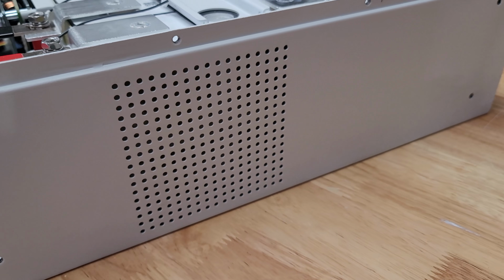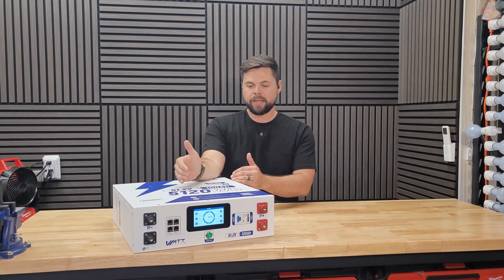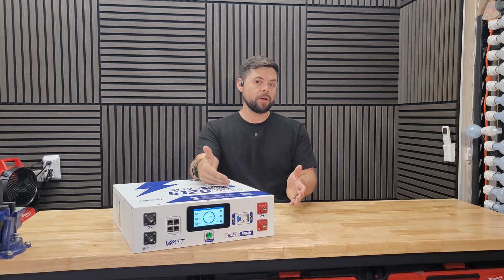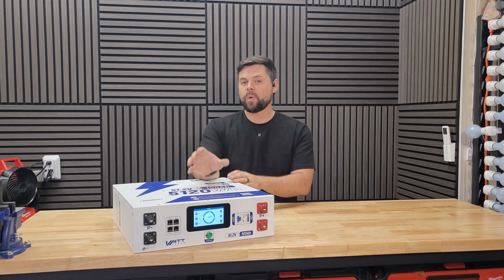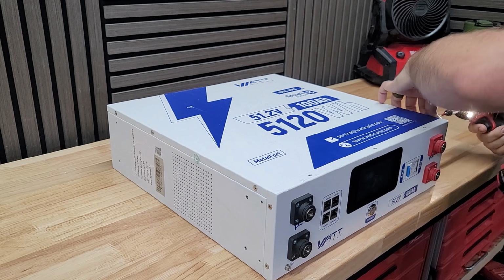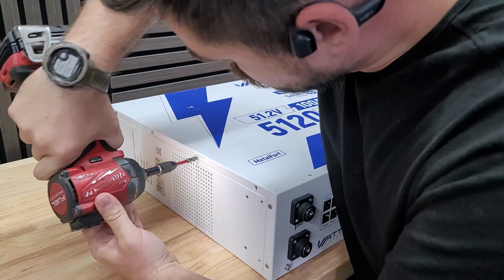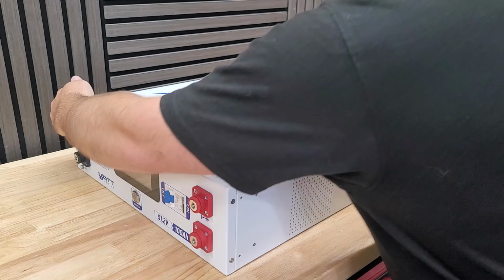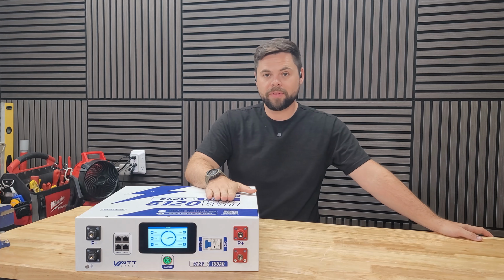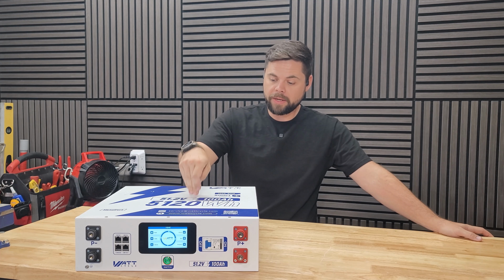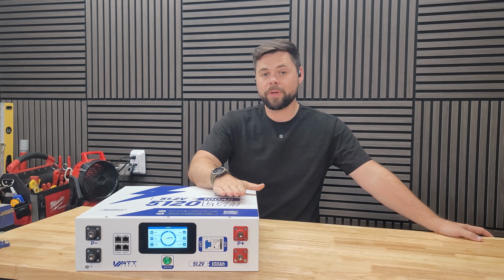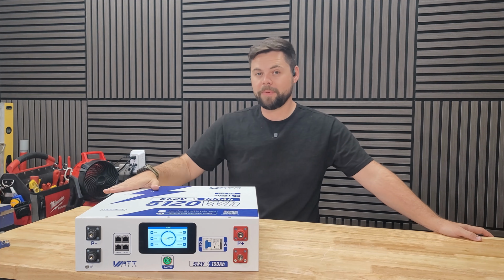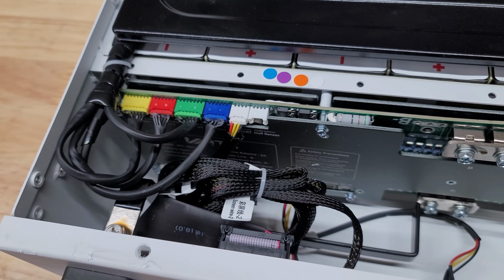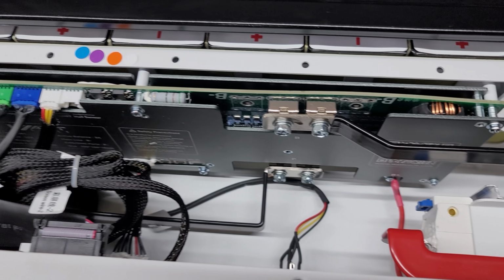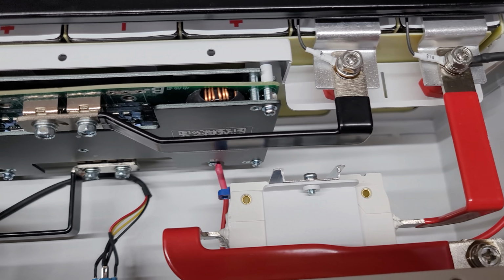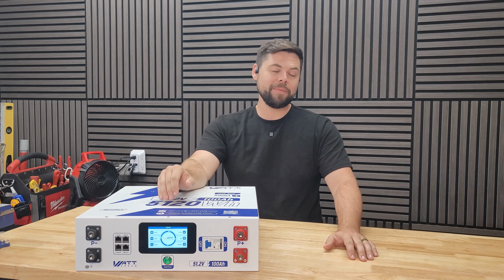Some brands put their batteries inside the casing in a way that you can't check the QR codes on the cells to verify quality. To make sure WattCycle wasn't doing that, I cracked this open to see what was going on inside. At first, I found a nice black insulative layer to make sure the metal housing can't come in contact with the terminal bars on top of the cells, and all the wires had good protection, good routing, and were very well kept inside.